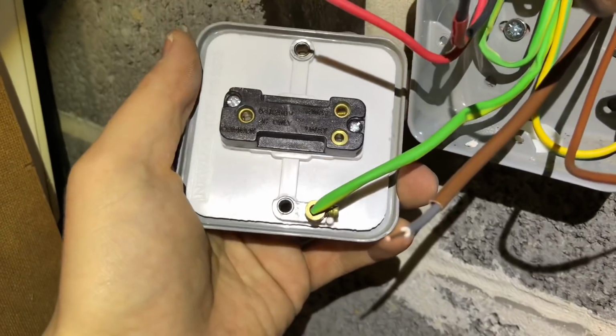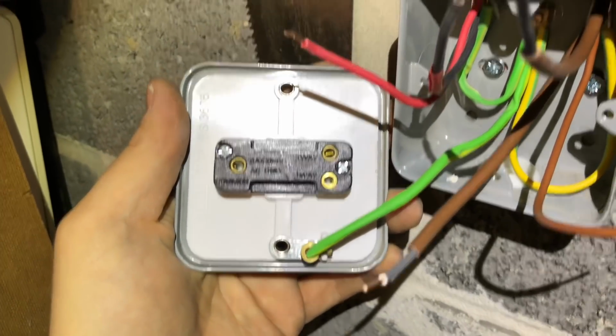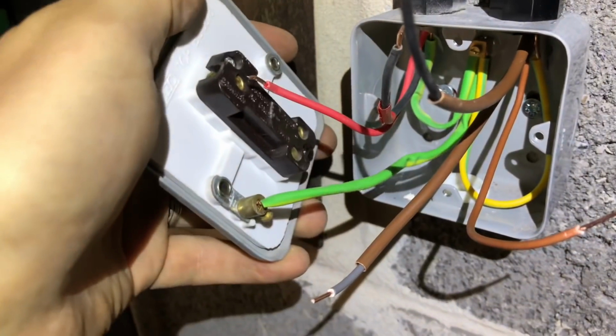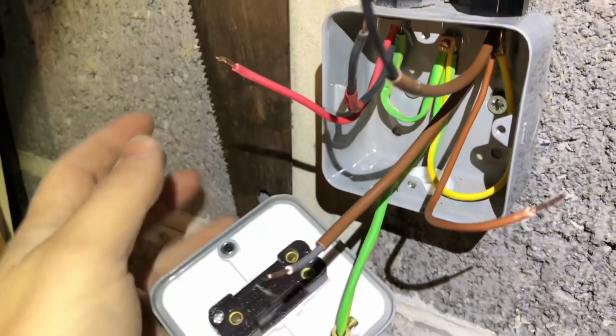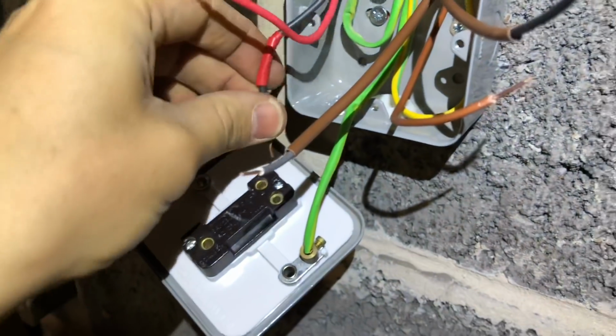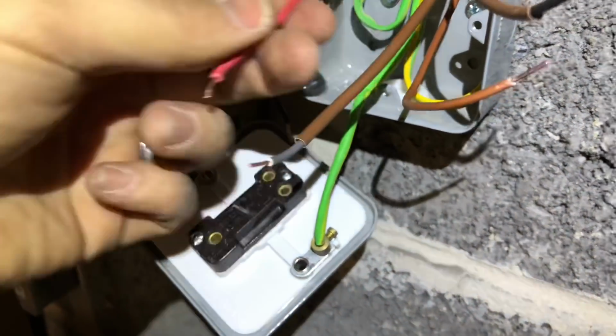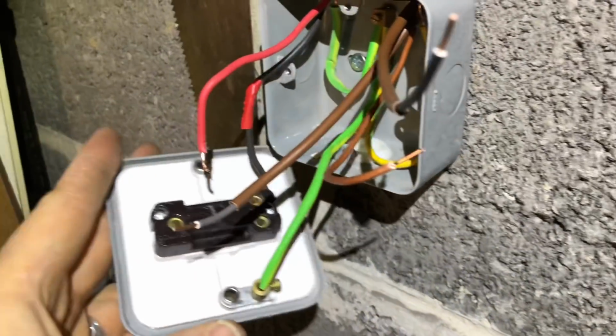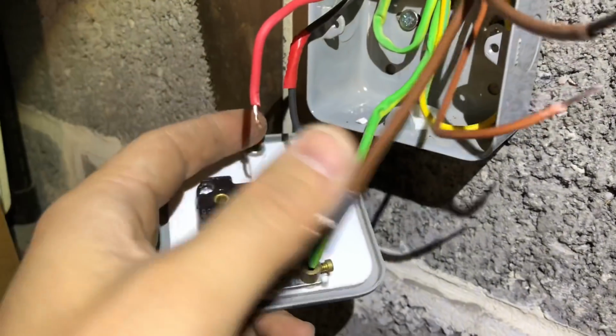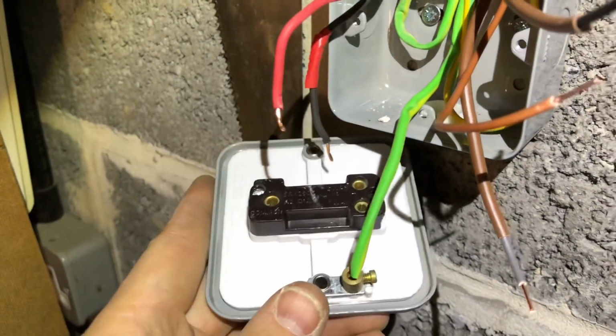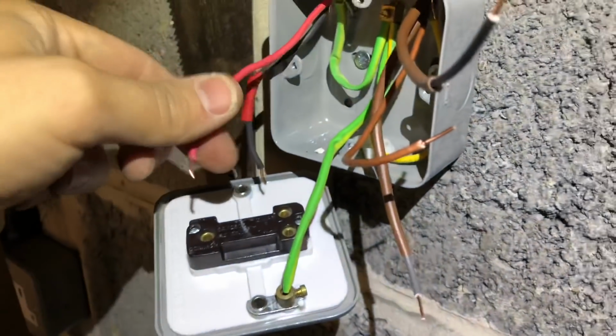So how do you connect it so that you can now convert to two-way switching? Well, currently the red conductor was in the common terminal and the black was in L1, and that was just acting as a one-way switch. But you can see this switch is a two-way switch, so it's got an L2 terminal as well.